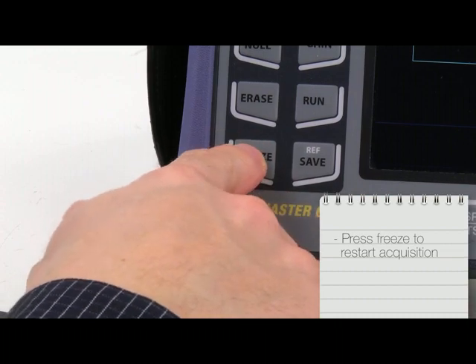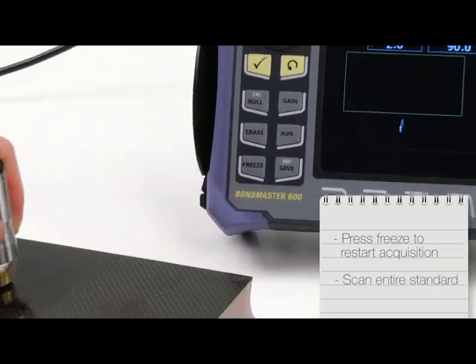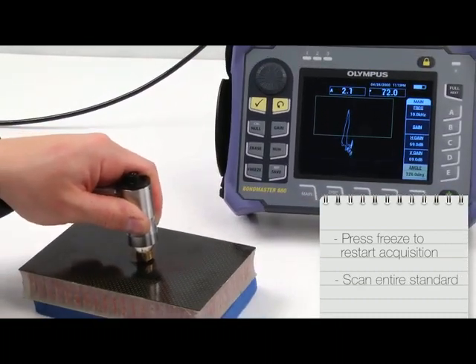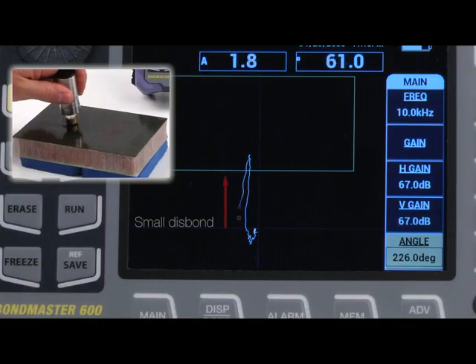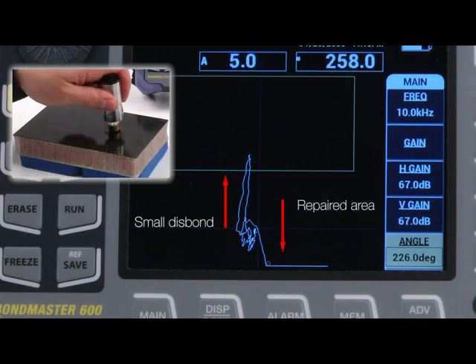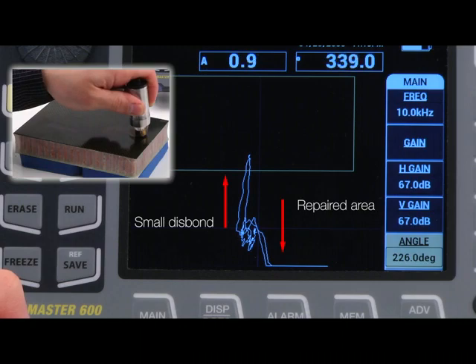Press Freeze again to restart acquisition and scan the entire standard. In this example, the small disbond goes upward on the screen while a repaired area goes down, enabling indications to be easily identified.